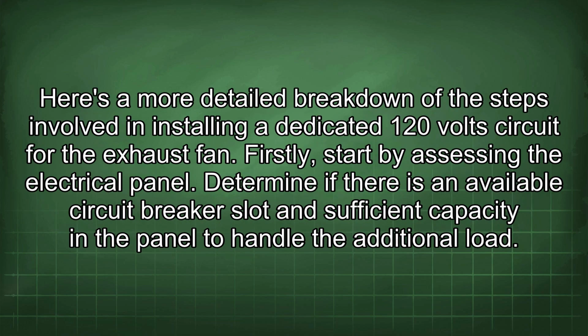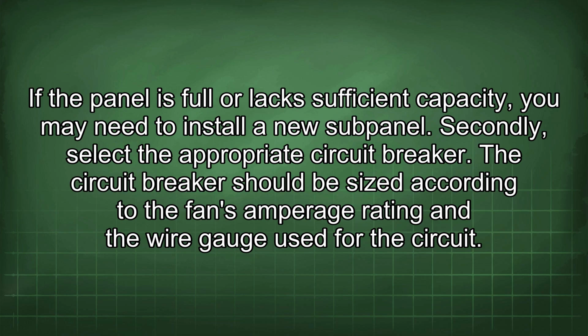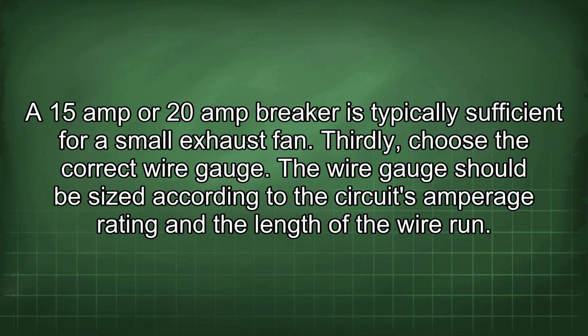Here's a more detailed breakdown of the steps involved in installing a dedicated 120-volt circuit for the exhaust fan. Firstly, start by assessing the electrical panel. Determine if there is an available circuit breaker slot and sufficient capacity in the panel to handle the additional load. If the panel is full or lacks sufficient capacity, you may need to install a new subpanel. Secondly, select the appropriate circuit breaker. The circuit breaker should be sized according to the fan's amperage rating and the wire gauge used for the circuit. A 15 amp or 20 amp breaker is typically sufficient for a small exhaust fan.